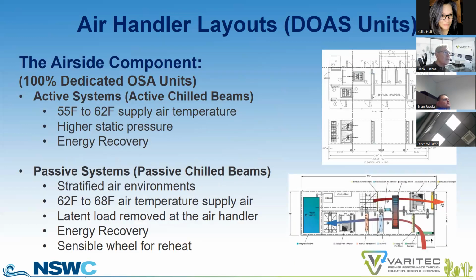Dedicated outdoor air units for active chill beam systems will provide 55 to 62 degree supply air. If you provide higher than 62 degrees, you need to make sure you are adequately dehumidifying the air at the cooling coil. A passive chill beam DOAS unit is unique because I can actually supply 62 to 68 degree air out of a passive chill beam DOAS unit. Again, providing the coil is properly selected and we're getting the dehumidification necessary to depress the supply air dew point.